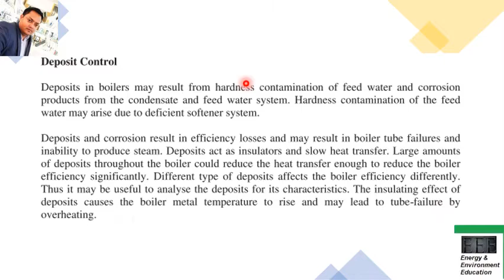In the exam also, friends, you can expect some question like, suppose, what is the effect of the presence of silica in boiler water? This is the type of question that you can expect in the exam, and in that case you have to write down what is the effect of silica in boiler water. The presence of silica in boiler water can give rise to formation of hard silicate scale. So basically the scale formation is happening here with the presence of silica in the boiler, and this is what is explained here. It can also associate with calcium and magnesium salts, forming calcium and magnesium silicates of very low thermal conductivity. Silica can give rise to deposits on steam turbine blades after being carried over either in droplets of water in steam or in volatile matter.